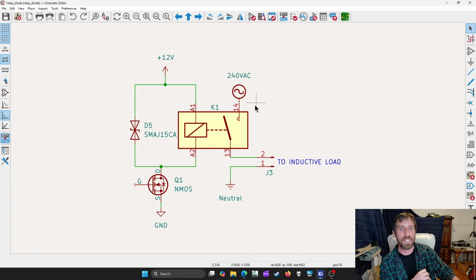If you're measuring AC with a probe, you need to make darn sure your probes are going in the right place. If your ground lead goes to line voltage, not only will you blow the probe potentially, but that's connected to earth ground, man. You're causing a short, and you're going to screw up your oscilloscope and potentially destroy it.